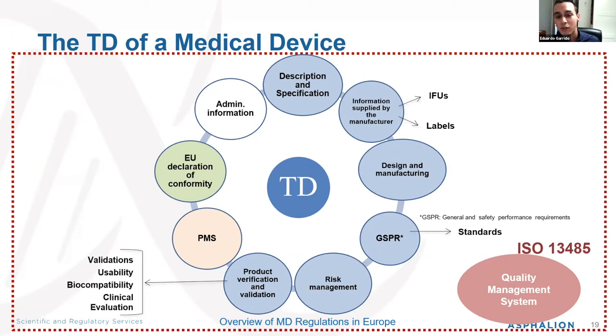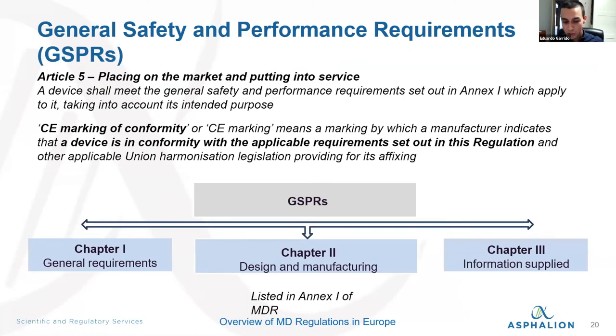Besides that, you also have to have a post-market surveillance plan in place, and finally you need a declaration of conformity. It's a lot of information, and all of it should be controlled within your quality management system, which, as I said, has to be based on ISO 13485.